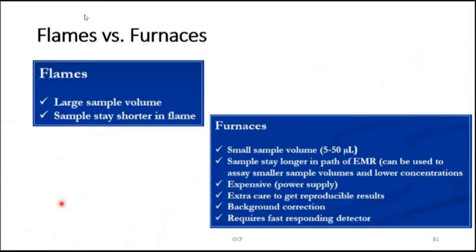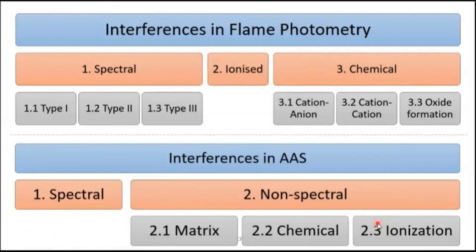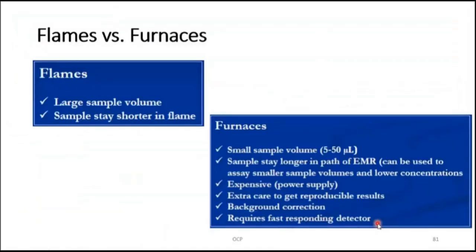Comparing flame versus furnace: for flames, large sample volume is required and samples stay in the flame for a shorter period of time. For furnaces, small sample volume (5–50 microliters) is required and samples stay longer in the path of electromagnetic radiation, giving better results. Furnaces can access smaller sample volumes at low concentration. However, furnaces are comparatively expensive, reproducible results are harder to achieve, background correction is needed, and fast-responding detectors are required.